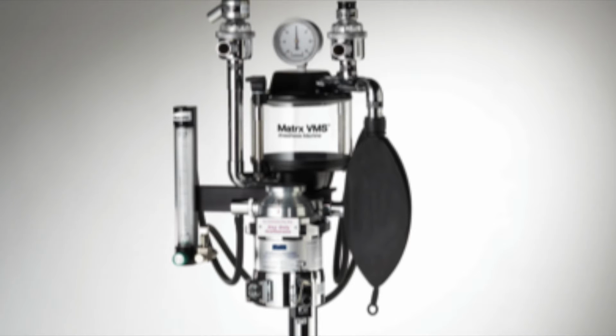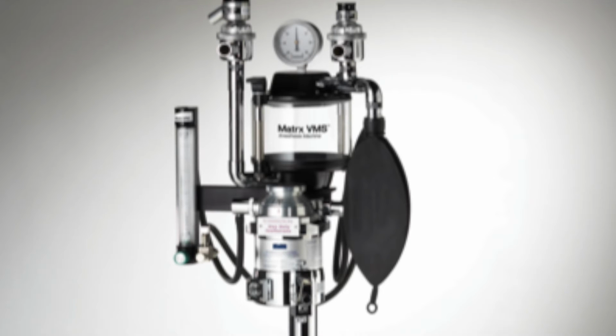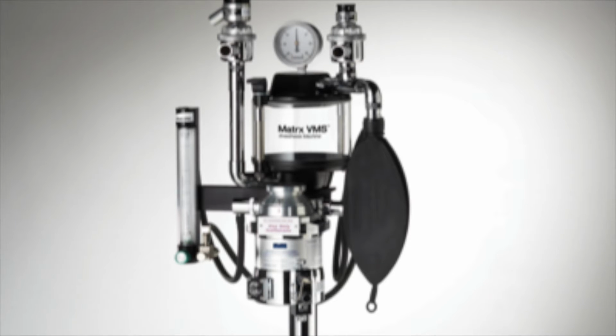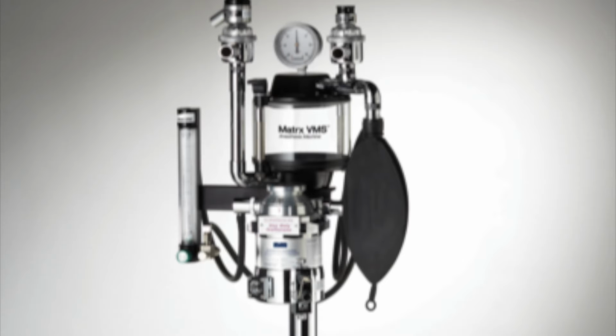Then, to the right of the exhalation unidirectional valve, we have the carbon dioxide absorbing canister. It contains calcium hydroxide, which combines with carbon dioxide exhaled from the patient and yields water from a chemical reaction, heat, and calcium carbonate, which is also known as limestone. We want to change the granules at least every 8 hours of anesthesia. Evidence of exhaustion of the granules is a color change from white to a purple-blue, but it can then turn back to white.